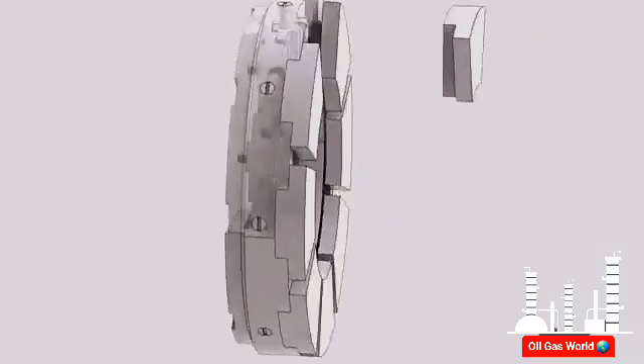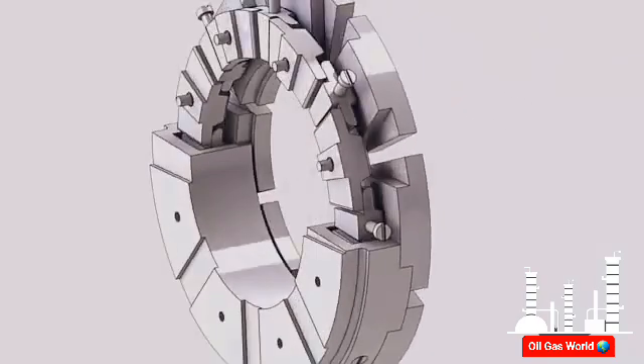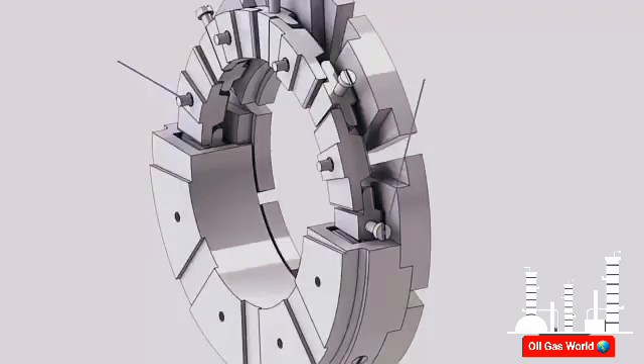The leveling plates are functionally small levers. They align the bearing pads with the thrust runner and equalize the load among the pads, despite any possible slight misalignment of the shaft axis from the normal. The leveling plates are mounted on the base ring by dowels and screws, such that the plates are free to tilt on their fulcrums.